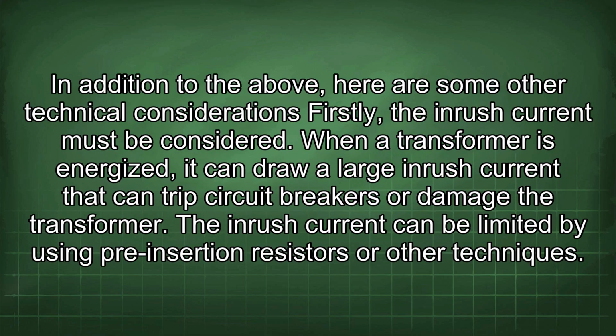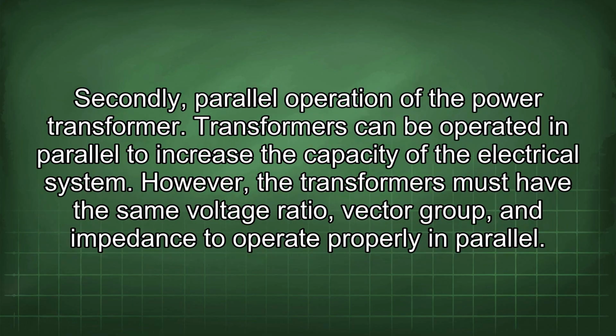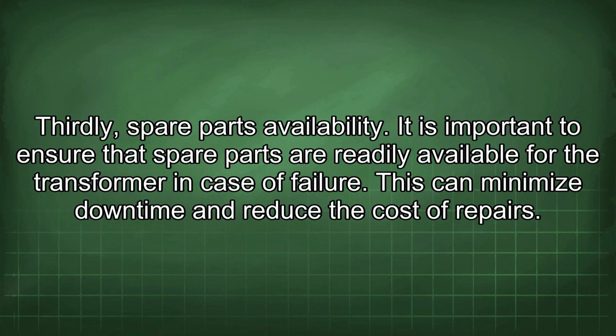In addition to the above, here are some other technical considerations. Firstly, the inrush current must be considered. When a transformer is energized, it can draw a large inrush current that can trip circuit breakers or damage the transformer. The inrush current can be limited by using pre-insertion resistors or other techniques. Secondly, parallel operation of the power transformer. Transformers can be operated in parallel to increase the capacity of the electrical system. However, the transformers must have the same voltage ratio, vector group, and impedance to operate properly in parallel. Thirdly, spare parts availability. It is important to ensure that spare parts are readily available for the transformer in case of failure. This can minimize downtime and reduce the cost of repairs.